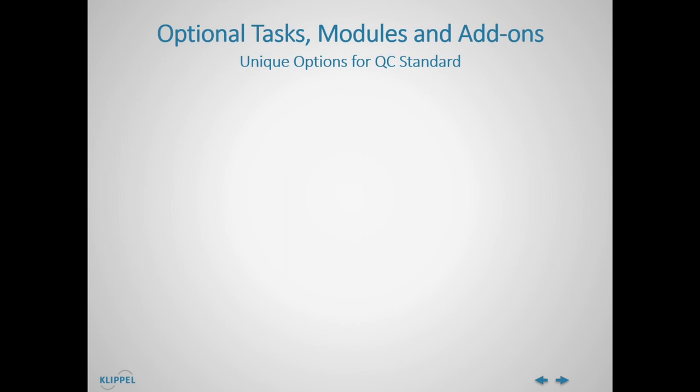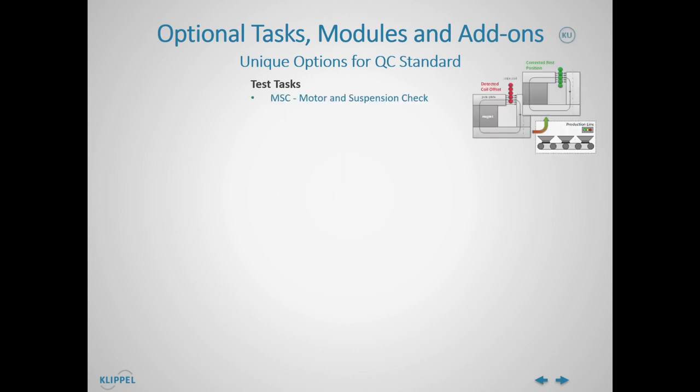The QC Standard software can be flexibly extended by various unique test tasks, add-on features, or post-processing tools to take your QC testing to the next level. First, we have the test tasks — additional test steps that can be added to your test sequence. We have the Motor and Suspension Check, the sibling of the famous Klippel LSI of the R&D system, for nonlinear parameter testing such as voice coil offset.